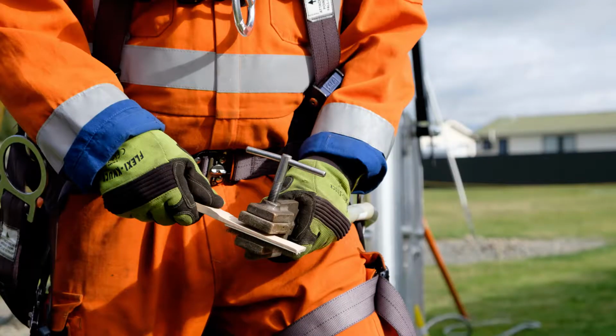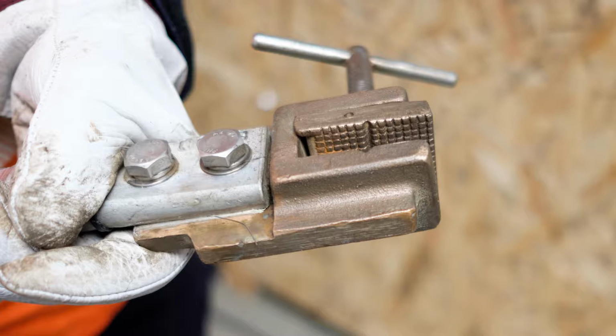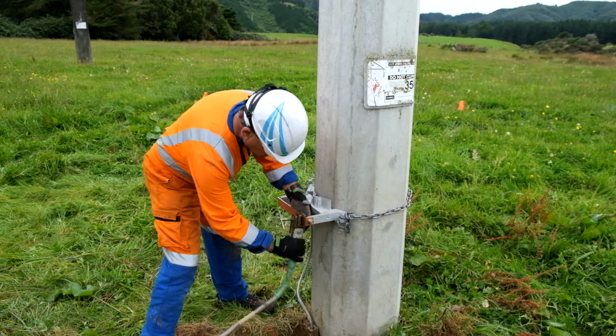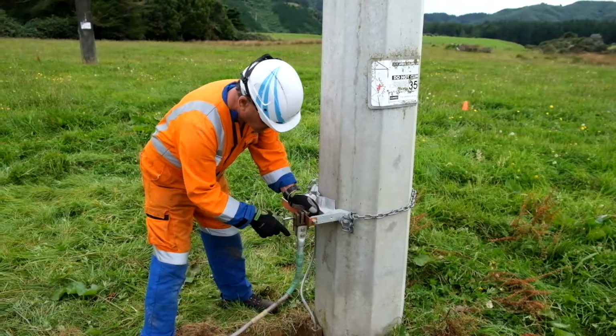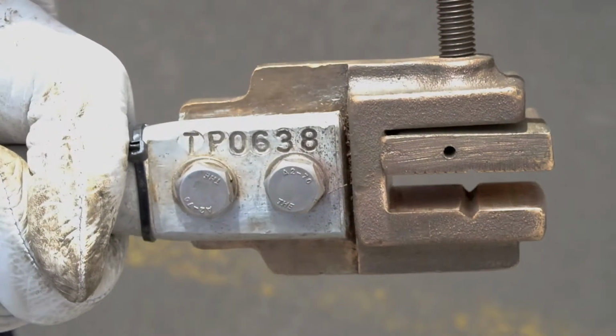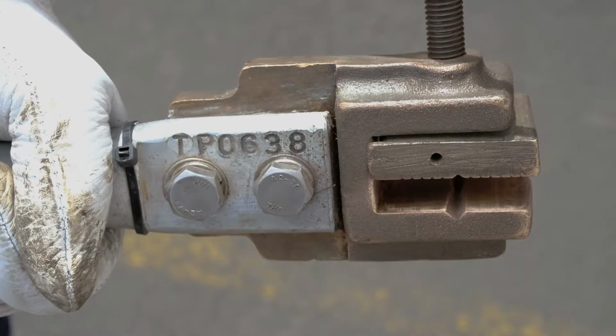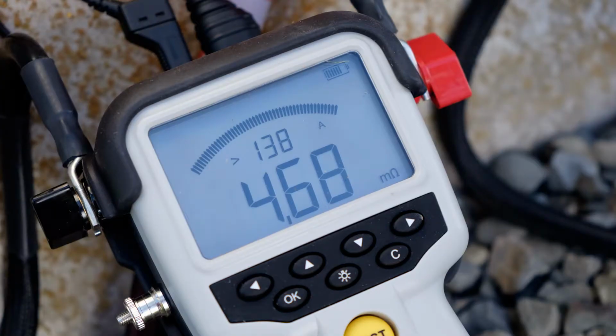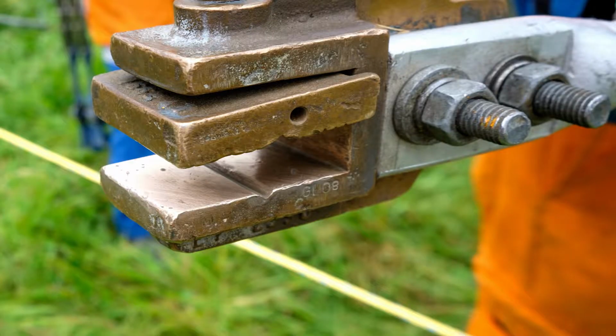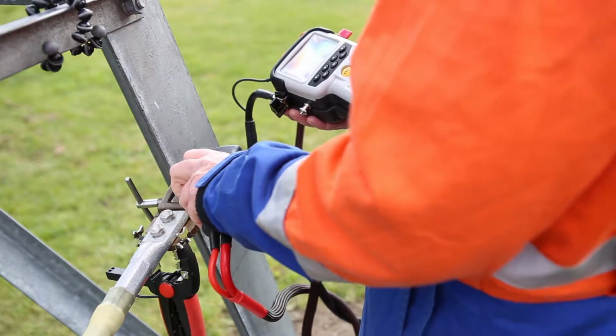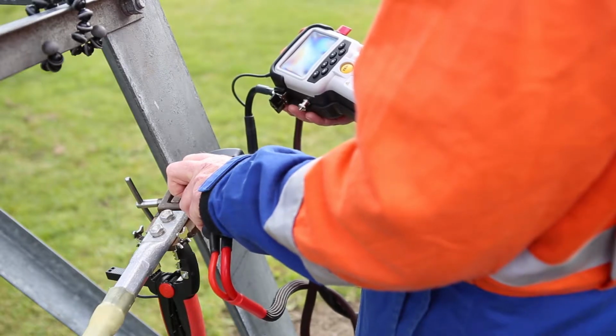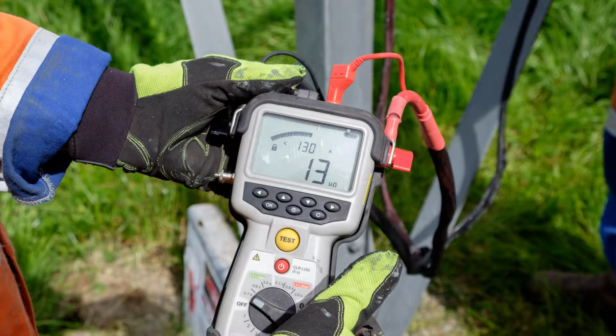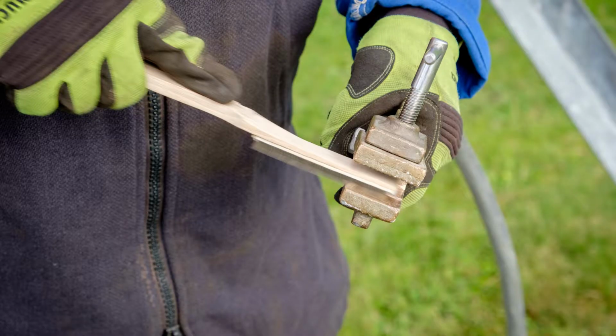A clean tail clamp is essential for your safety. Tail clamps are made with a knurled or patterned clamping jaw on the side that moves. This side provides the grip. The other smooth fixed jaw is designed to carry fault current. Recent tests have shown that simply cleaning the tail clamp's fixed contact surface dramatically improves conductivity, meaning that the equipment works as it was designed to, keeping you and your team safer in the event of an accidental livening or induction.